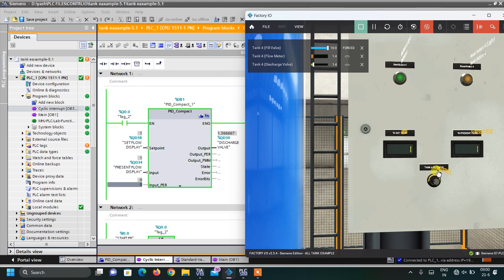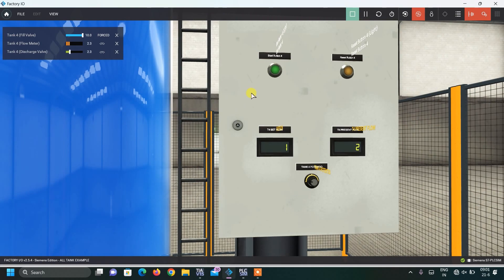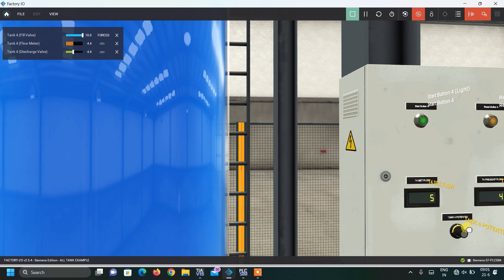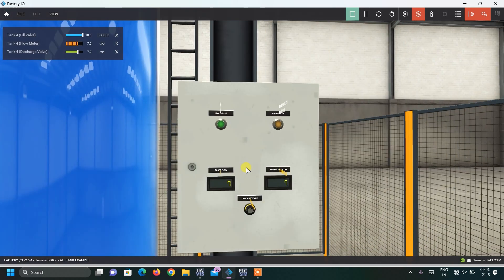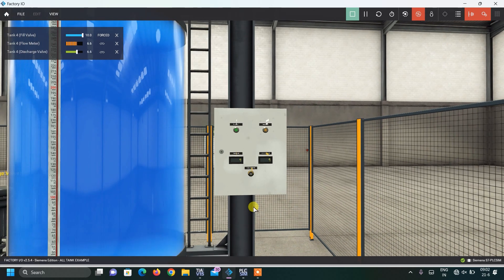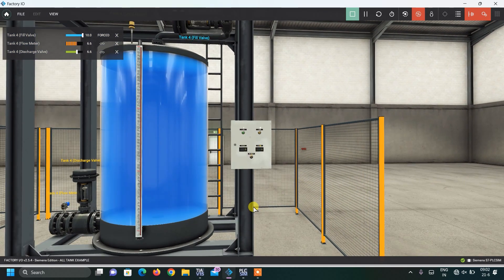The value approaches the set point. If I reduce the setpoint the output slowly reduces and comes near the new set value, with minimal oscillations. This demonstrates the PID flow controller with input, output monitoring visible. Setting the target to 7, the discharge valve opens accordingly and the flow slowly reaches near 7. There may be a small error of about 1 in simulation, but the controller reaches and maintains the set point. This is flow control in Factory IO using a PID controller programmed in TIA Portal.